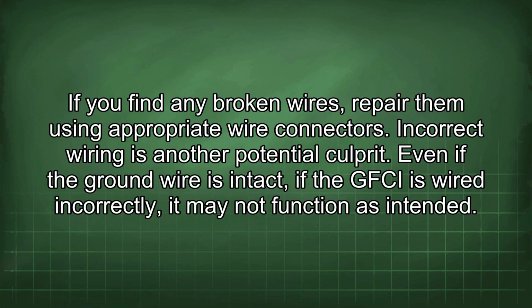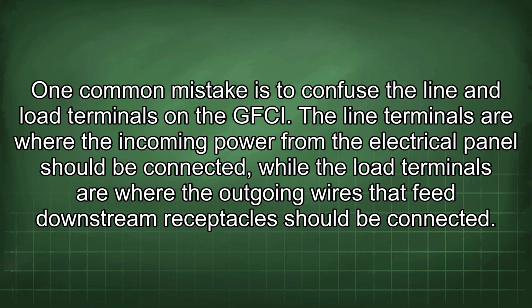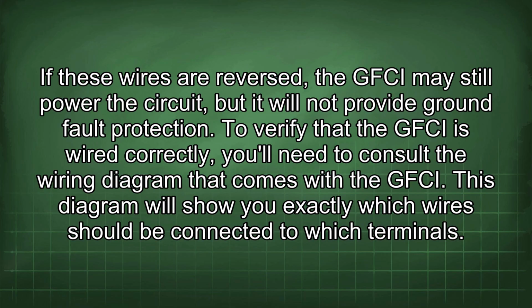Incorrect wiring is another potential culprit. Even if the ground wire is intact, if the GFCI is wired incorrectly, it may not function as intended. One common mistake is to confuse the line and load terminals on the GFCI. The line terminals are where the incoming power from the electrical panel should be connected, while the load terminals are where the outgoing wires that feed downstream receptacles should be connected. If these wires are reversed, the GFCI may still power the circuit, but it will not provide ground fault protection.